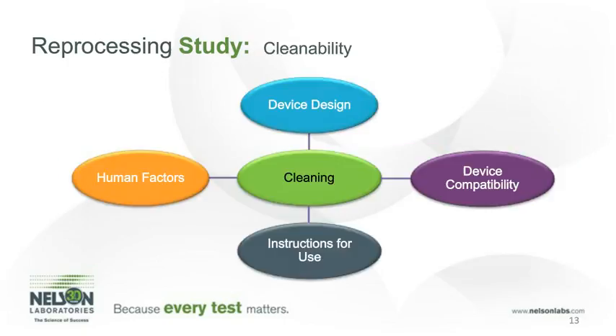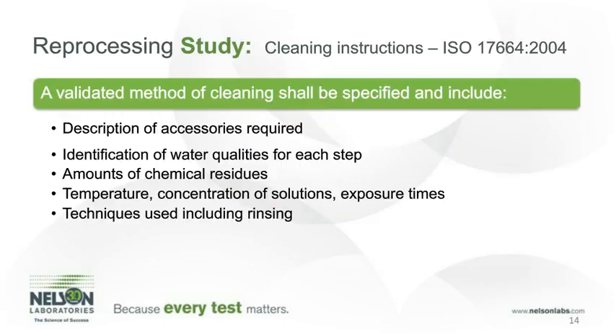Cleaning depends on 4 criteria. They include device design, device compatibility, instructions for use, and human factors. One very important standard is ISO 17664. It states a validated method of cleaning shall be specified and include a description of accessories required, the identification of all water qualities that are utilized for each step of the process, the amounts of chemical residuals that are tested after the cleaning process is performed, and also information regarding the temperature, concentration of solutions, and exposure times, and all of the techniques utilized in the cleaning procedure, including rinsing.